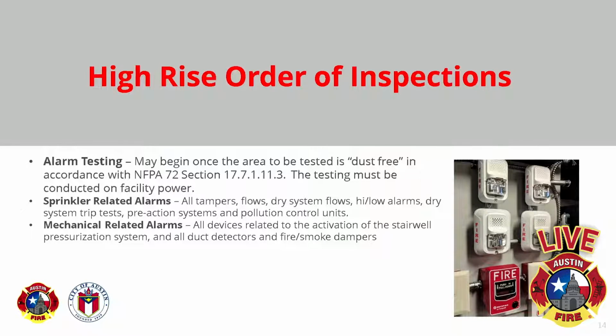Mechanical related equipment, that's the variable. Every building has its own issues with mechanical. Some are office buildings that are not shells but built out as finished buildings. They could have as many as 50, 60 duct detectors on a floor. If there's 50, 60 duct detectors on a floor, that floor alone is probably going to take half a day, because we test every one. The units have to be running when we test them so we can see them shut down. So obviously, this is going to be later on in the game. If they're controlled by a central unit, all of the programming has to be done prior to us inspecting those duct detectors.